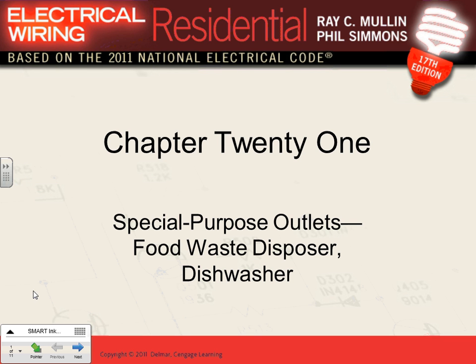We said dedicated circuit for the garbage disposal and dedicated circuit for the dishwasher. Based on the amp size, we could have put them on one circuit. Not a good idea though. Code-wise, you can't feed these two from the two small appliances circuit in the kitchen. You cannot. So you have to bring either one circuit to feed both of them if they can fit, or you have to give them a dedicated circuit each. We decided to give them a dedicated circuit because that's the best design. Has everybody got that, guys? So that's basically what we're going to talk about.